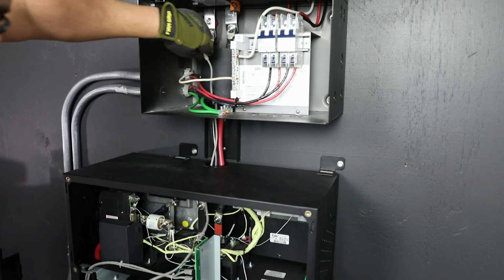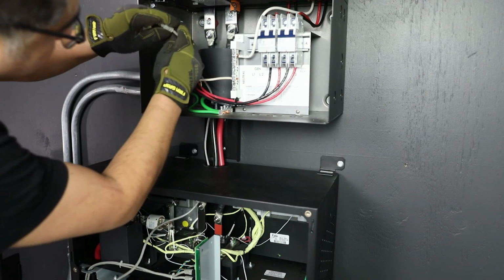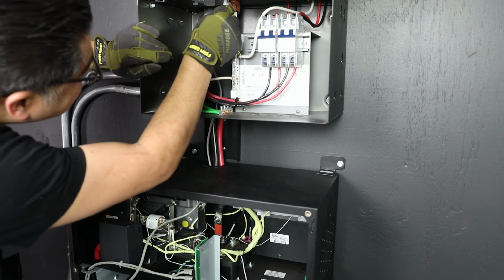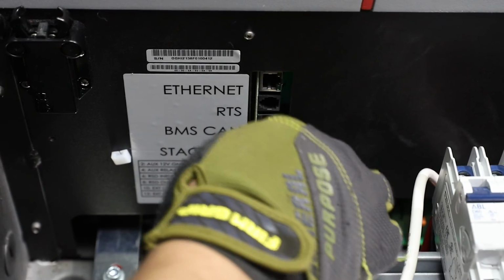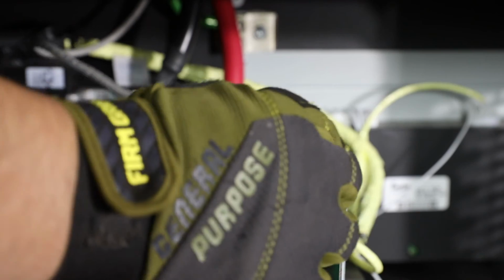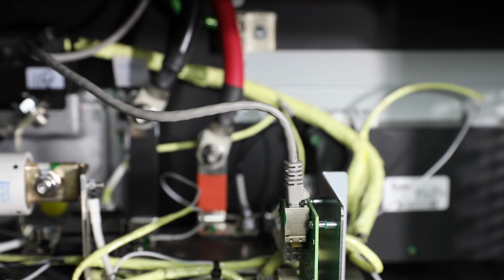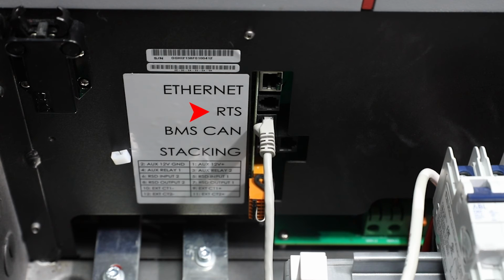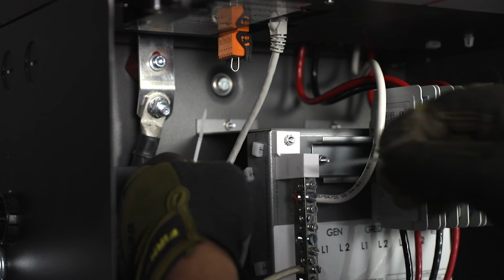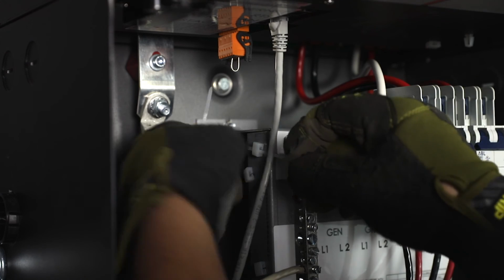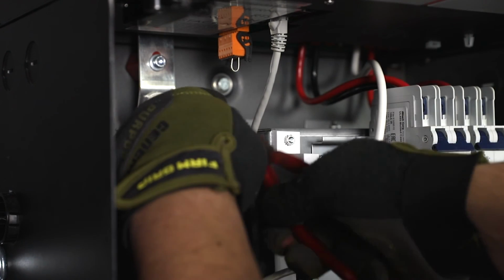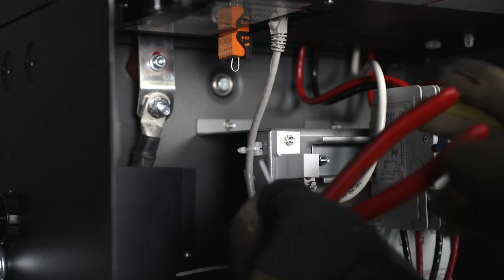Connect the communications cable in the BMS port of the battery. Route through the raceway and connect to the BMS CAN port of the inverter. Note, do not connect a remote temperature sensor, or RTS, unless you are installing a lead-acid battery. Connect the network cable for direct user interface connectivity, if it applies. Secure all communications cable using zip ties, ensuring these do not touch any battery or AC conductors.